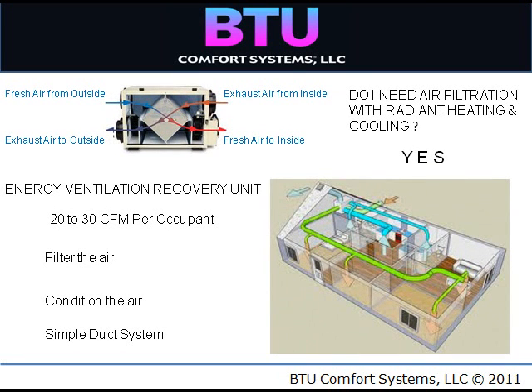A single-source radiant system can provide both your heating and cooling. To keep the air fresh and filtered, air movement must be achieved. In this example, an ERV is used. They are simple devices requiring minimal ducting. You may elect to provide a substantially downsized conventional air system for filtration, and the radiant heating and cooling is the primary conditioning source. Say, for example, a 5-ton unit, you might put 2 tons of air and 3 tons of radiant heating and cooling. Stage these mechanical systems, and you get the best of both worlds.